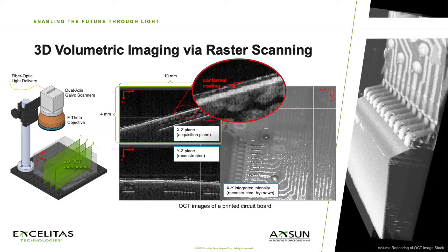By calibrating the optical scanner setup against a known reference and applying additional geometric distortion correction if necessary, high measurement accuracy on the order of tens of microns can be achieved in the XY dimension. In the Z dimension, the optical resolution is determined by the imaging laser's spectral range, and is typically less than 10 microns, but can approach 1 micron for some state-of-the-art OCT systems.